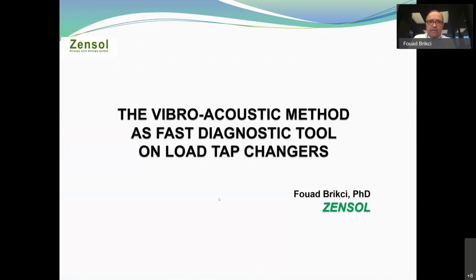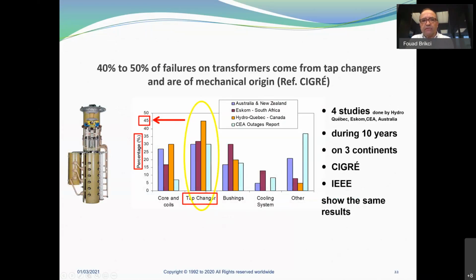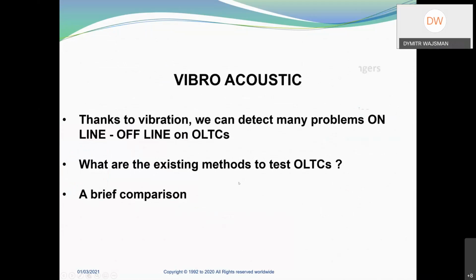So here, my presentation is focused on the vibroacoustic method as a fast diagnostic tool on load tap changers. More than 40 to 50% of failures on transformers come from tap changers and are of mechanical origin. We have the same numbers for the breakers. Thanks to vibroacoustic, we can detect many problems online or offline on OLTCs.